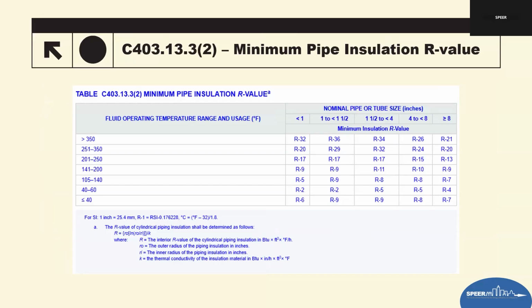So the second table is also providing minimum R values for this. The key concept here is that R value represents thermal resistance. So higher R values reduce heat loss or heat gain in the pipe, which improves its efficiency and protects against condensation, temperature drops, or equipment oversizing. These R values are dependent on the fluid type that is inside of the pipe itself. Temperature bands: fluid temperature is the primary driver for insulation performance, as we talked about earlier, but here are the specific requirements.